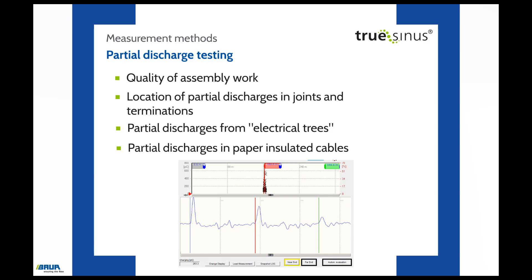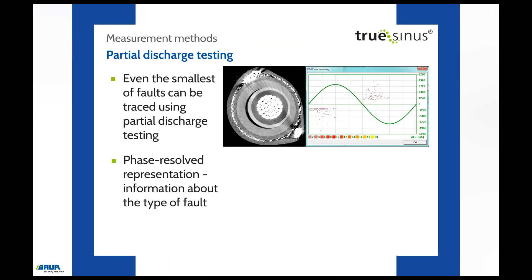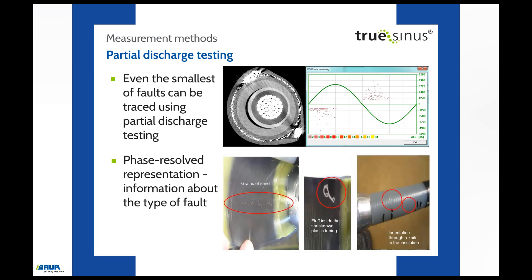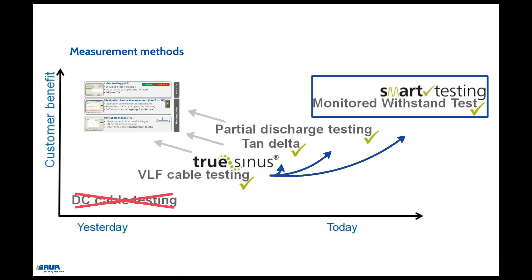Even the smallest of faults — for example, an air pocket between the insulating body and the field control — can be highlighted using partial discharge testing. The partial discharge testing also provides a phase-resolved representation, which gives information about the type of fault. This phase-resolved representation of the air pocket leads us to suspect that the cable contains a non-conducting material that is not in direct contact with the metal electrode.